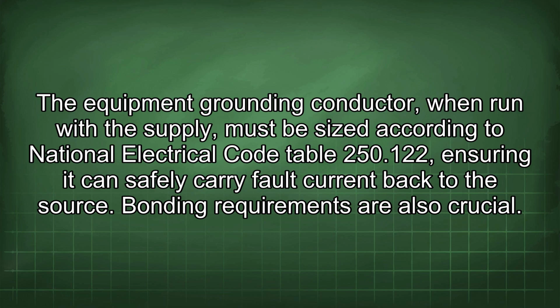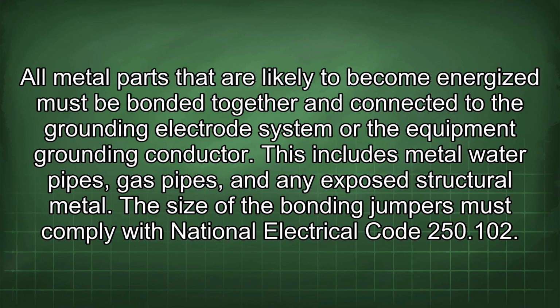Bonding requirements are also crucial. All metal parts that are likely to become energized must be bonded together and connected to the grounding electrode system or the equipment grounding conductor. This includes metal water pipes, gas pipes, and any exposed structural metal. The size of the bonding jumpers must comply with National Electrical Code 250.102.